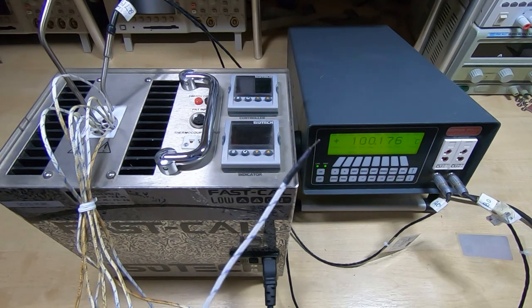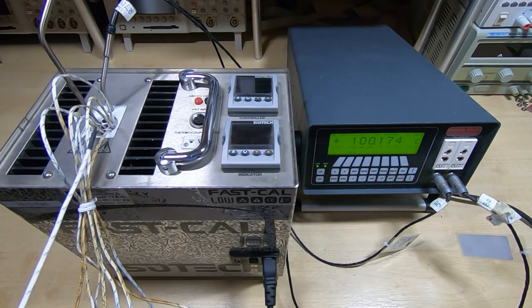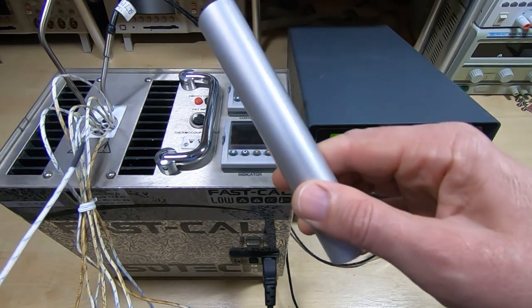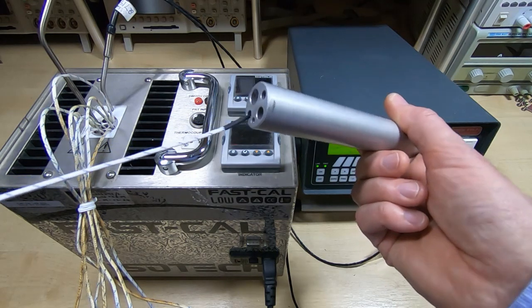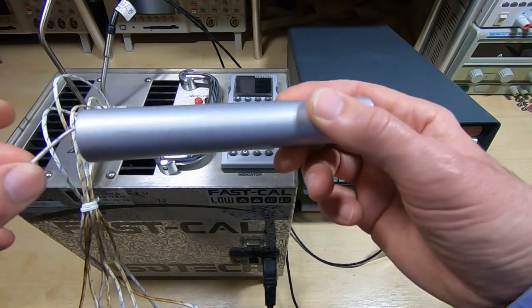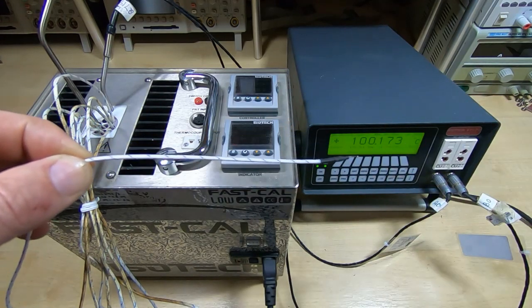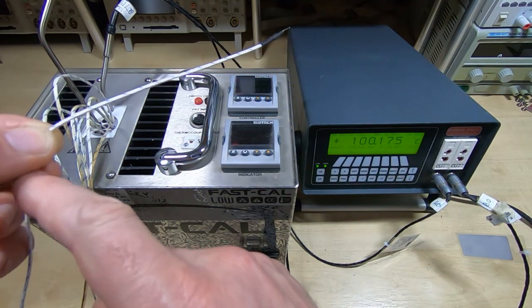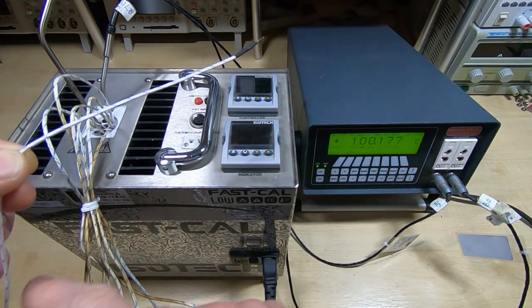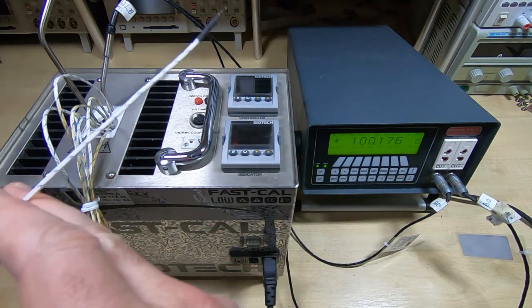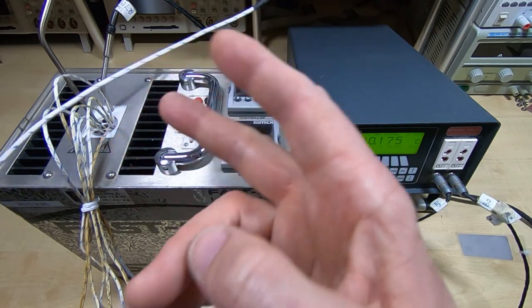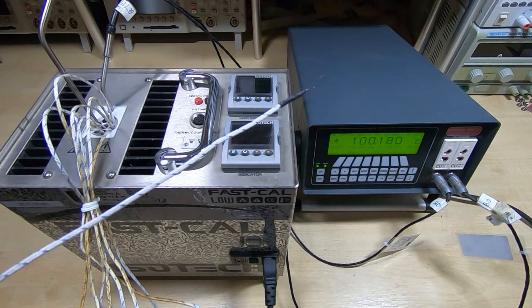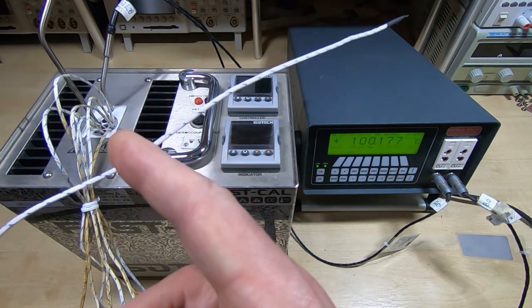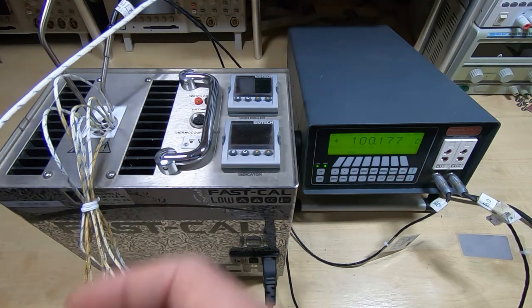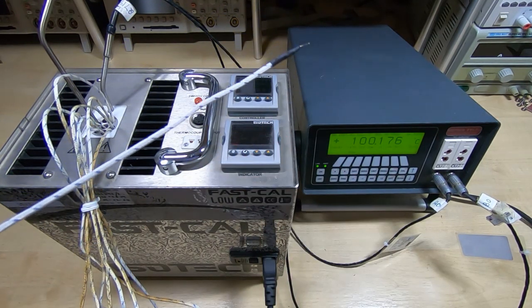Also, when calibrating probes, it's important that the equipment is suitable for what you're doing. So these wells are very deep, so if I look at one of the inserts, you can see that the actual sensor goes down a very long way into the block, and that's to make sure that there's no conduction of heat from the outside world or to the outside world when you're trying to heat or cool the probe. And that is important. If you're getting an outside influence, then that's going to vary depending on the ambient conditions, and so if you were inserting this into a reflow oven, for example, the outside air temperature could have a major bearing on this in terms of accuracy if you hadn't eliminated that as part of your calibration process.